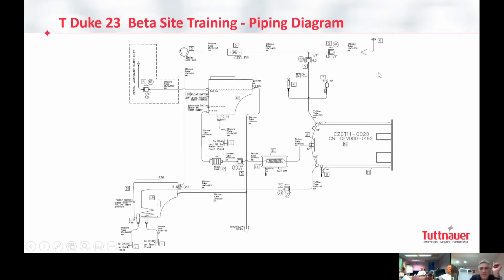In Elara, it was continuous: every 40 seconds, there were 6 seconds of maintenance. 2 seconds this one is closed, 2 seconds this one is open, then it gets closed, then you wait another 2 seconds, and then again it opens. And then the vacuum keeps going from here. Here, it's not continuous, but only when the controller feels it is needed. This is in order to save time. Sometimes you don't need this maintenance because there is no condensation. When there is condensation, the controller will feel that the speed at which the vacuum is reached is not sufficient. Then it will go for this maintenance.